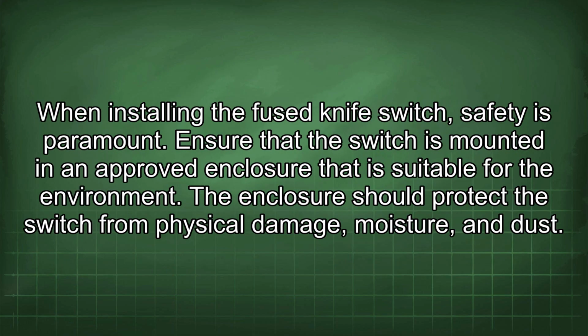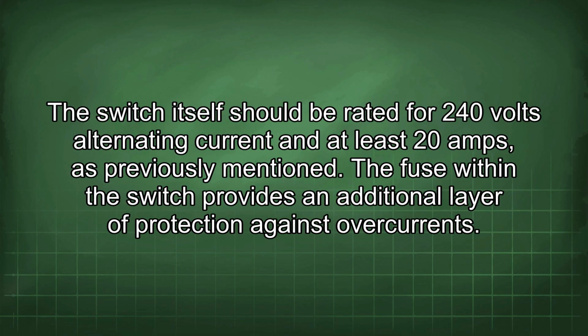When installing the fused knife switch, safety is paramount. Ensure that the switch is mounted in an approved enclosure that is suitable for the environment. The enclosure should protect the switch from physical damage, moisture, and dust. The switch itself should be rated for 240 volts alternating current and at least 20 amps, as previously mentioned. The fuse within the switch provides an additional layer of protection against overcurrents.